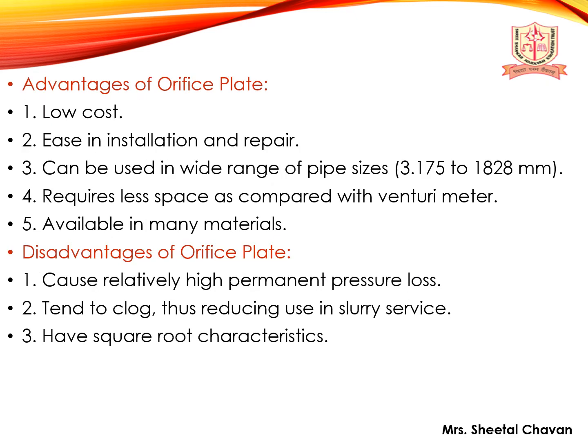Advantages of orifice plate: low cost, easy installation and repair, can be used in a wide range of pipe sizes, requires less space compared to a venturimeter, and is available in many materials. Disadvantages: it causes a relatively high permanent pressure loss, tends to clog when used in slurry service, and has a square root characteristic.